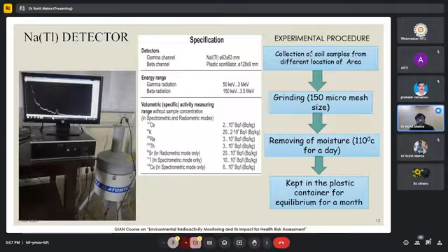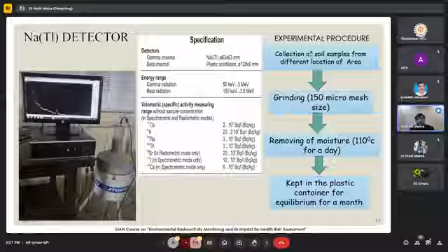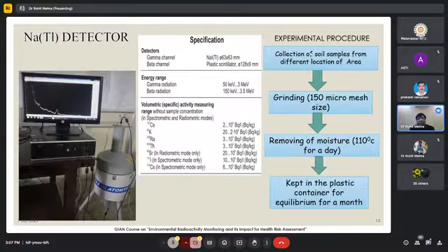So there are two important parameters which one should remember: your detector cannot have similar efficiency for all the energy values. If you are measuring energy 609 keV, the efficiency of the same detector will be different for measuring the energy of 1461 keV.